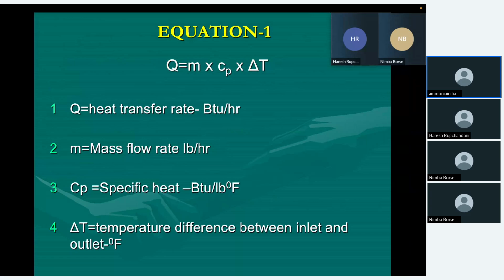Now let us see what are the equations we use for calculation of condensers and chillers. The two main equations: the first is Q, the heat transfer rate in BTU per hour, equal to M, the mass flow rate in pounds per hour, into specific heat in BTU per pound per degree Fahrenheit, and delta T, the temperature difference between inlet temperature and outlet temperature of water. For example, normally in India our wet bulb temperatures are around 28 degrees centigrade. So water entry temperature is 32 degrees centigrade, outlet temperature is 36 degrees centigrade, and condensing we normally design at 40 degrees centigrade. With evaporative condensers, you can go as low as 38 degrees centigrade.